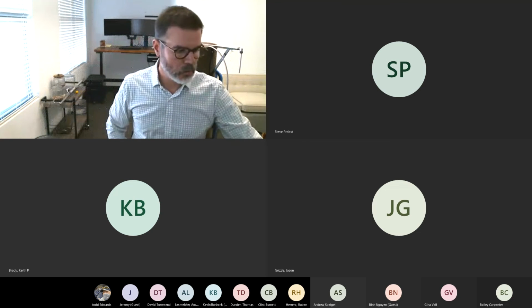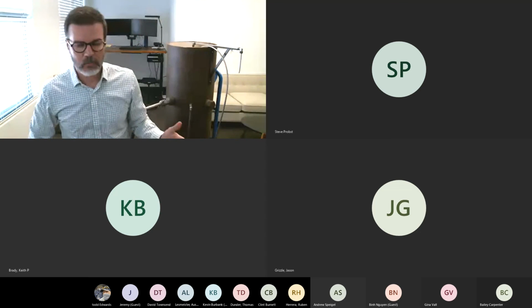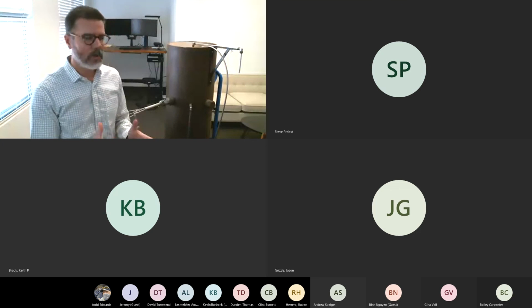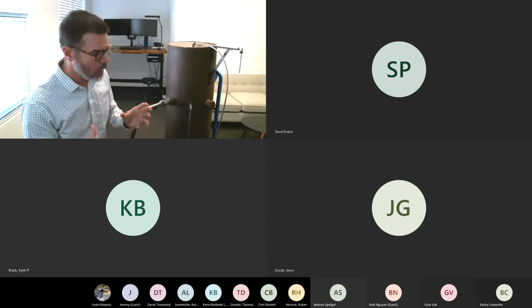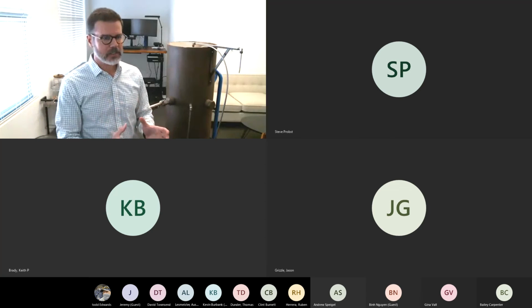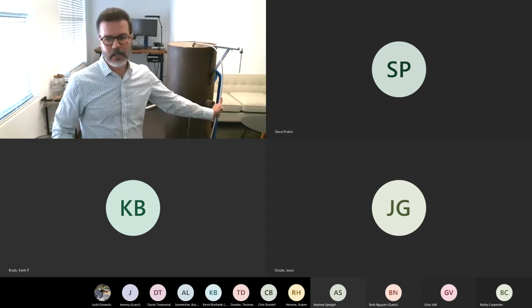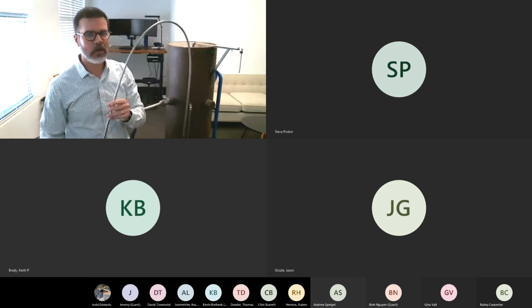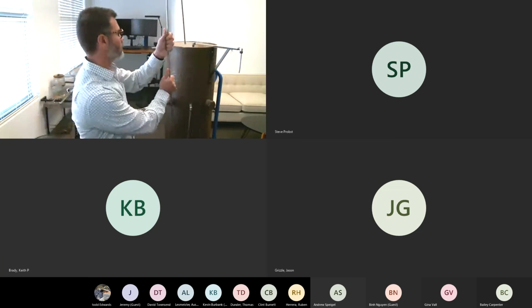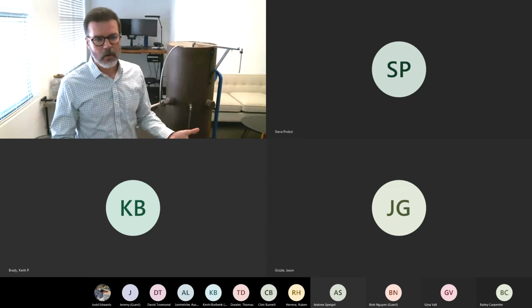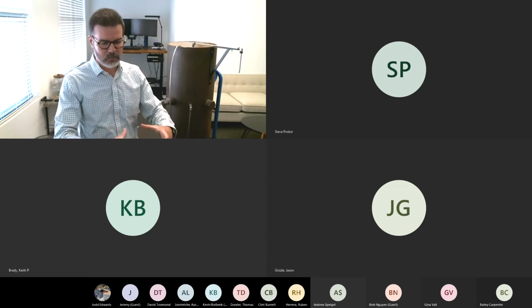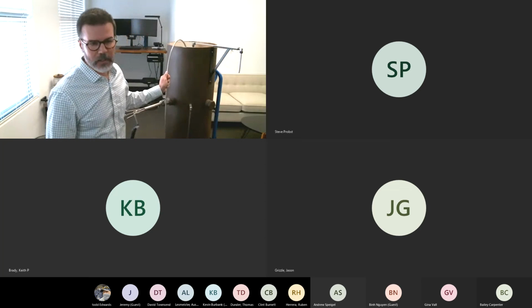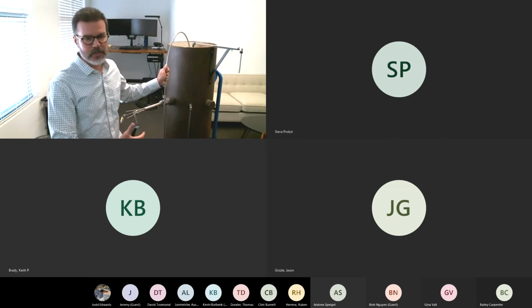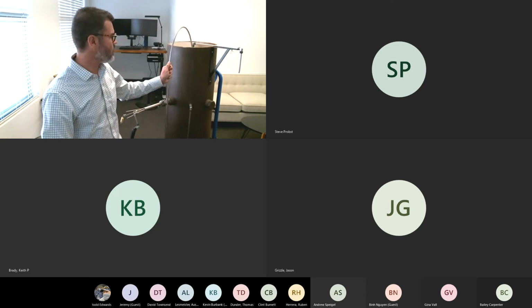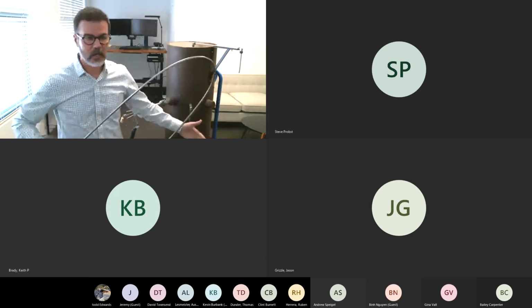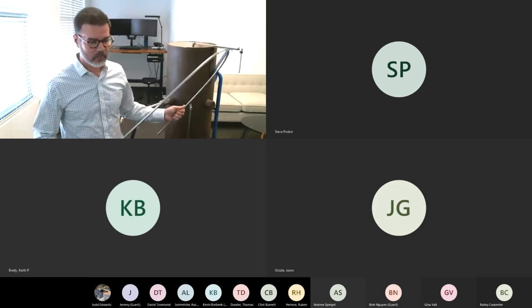Again, there are specific scenarios in which you can use a rake probe, and how you use it, how you configure it. You want to make sure that you've got that criteria met specifically. So going back to alternate method 061, single point stack testing, the way that was typically handled was by throwing what is called a shepherd's hook over the top of the stack, sampling from the centroid area of the stack. Centroid area is defined as 10% of the center of the stack. And so this was the most commonly used way to sample for engine testing. And in 2014, again, the EPA revoked the allowance for this type of testing.